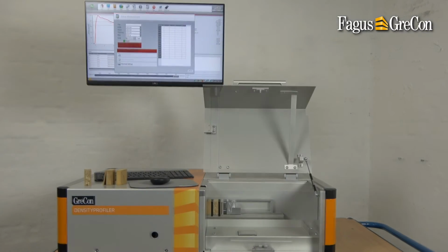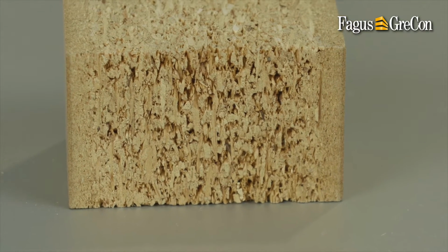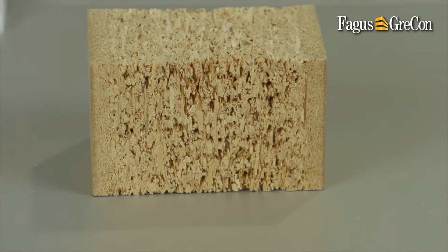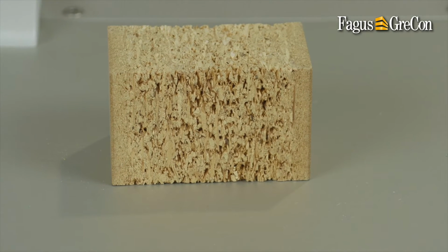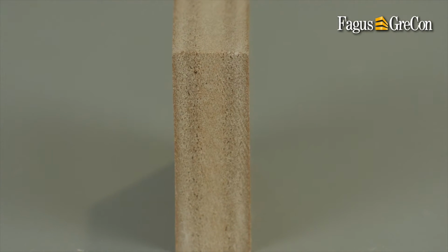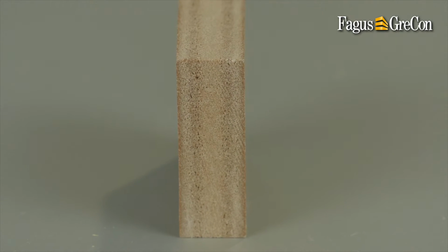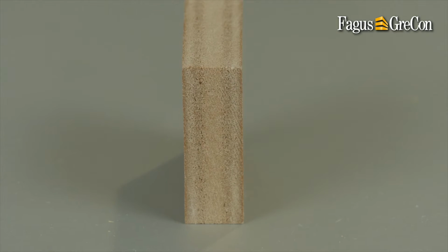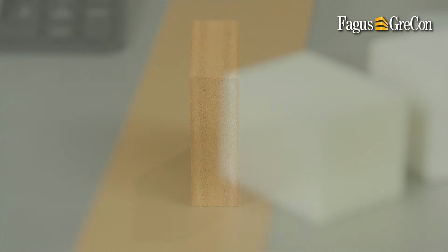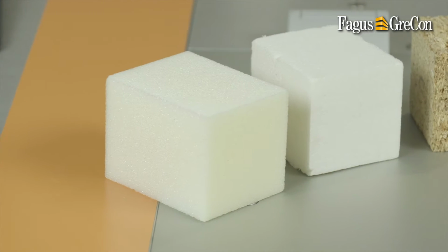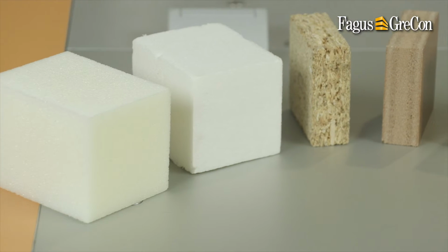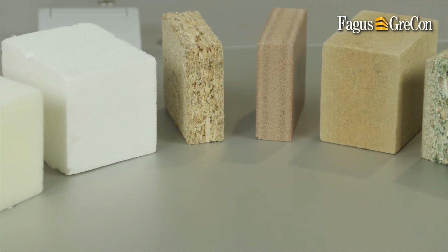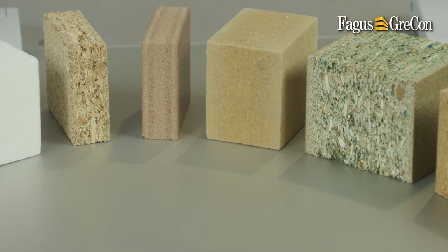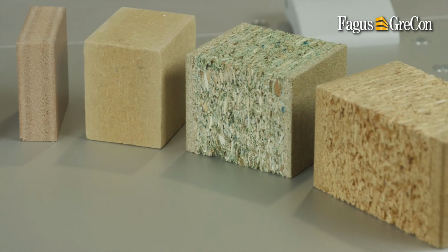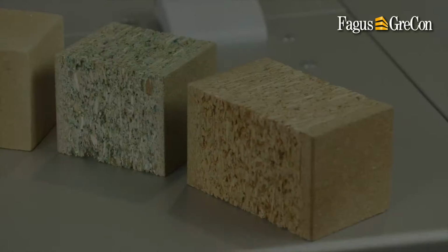The GreCon Density Profiler can measure materials with a low specific density and materials with a significantly higher density than standard MDF, OSB and particle board. These lower density materials include fiber insulation materials and modern composites. In addition, it is possible to measure higher density materials such as gypsum, cement and stone. The measuring range extends from 50 to 1500 kg per cubic meter.